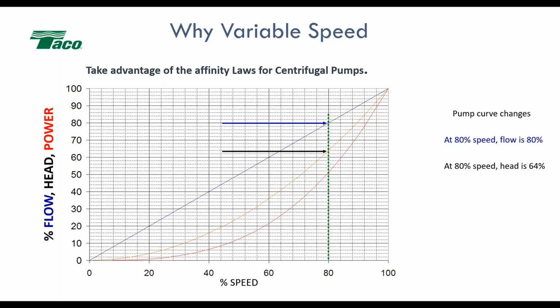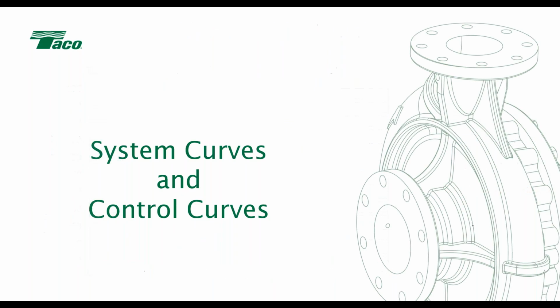So the head that pump will develop is 64% of what its design head was. And at 80% speed, the power draw is only 51%. So we changed the speed by 20%, but we got a 49% reduction in power draw. Okay, so it's a significant power drop with a fairly small speed change.